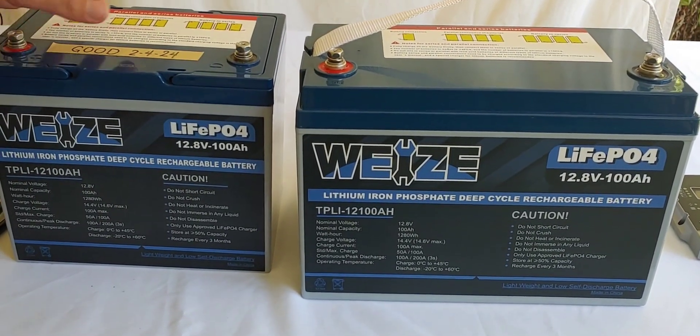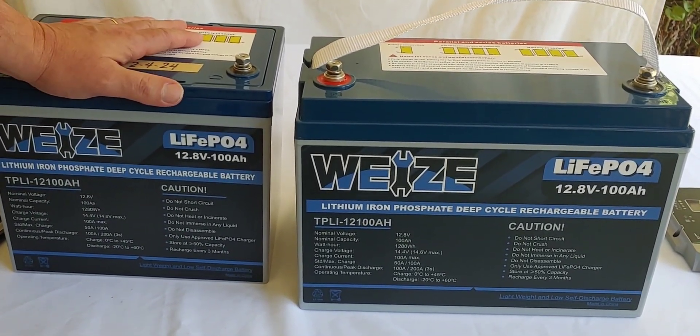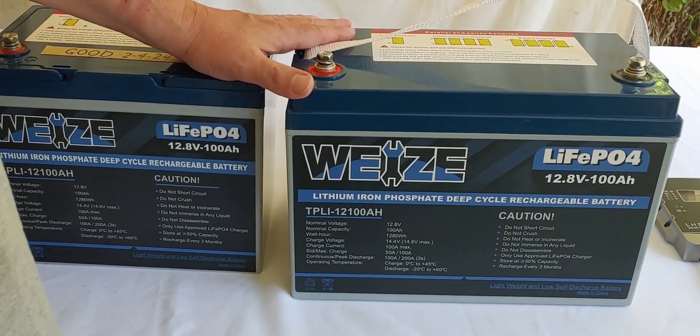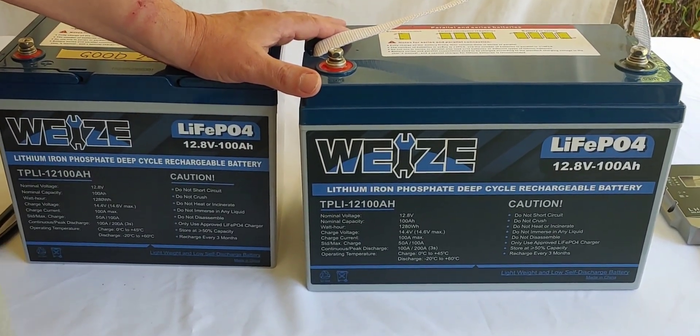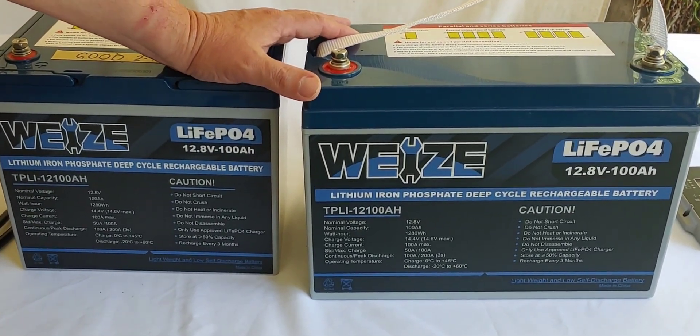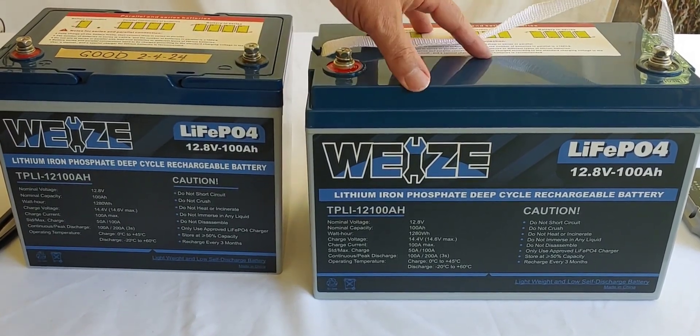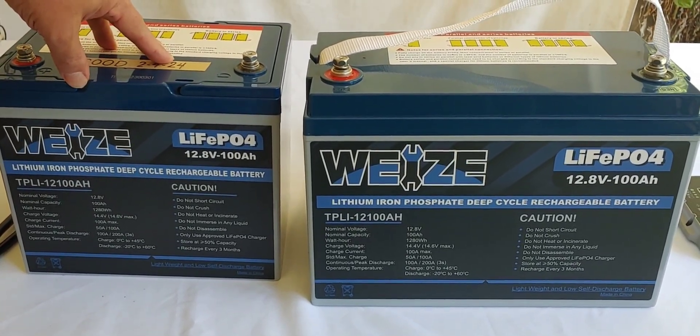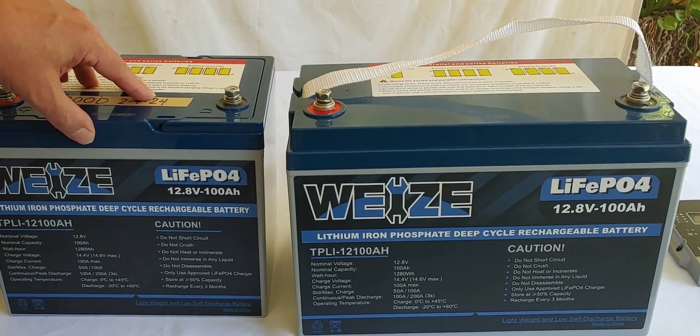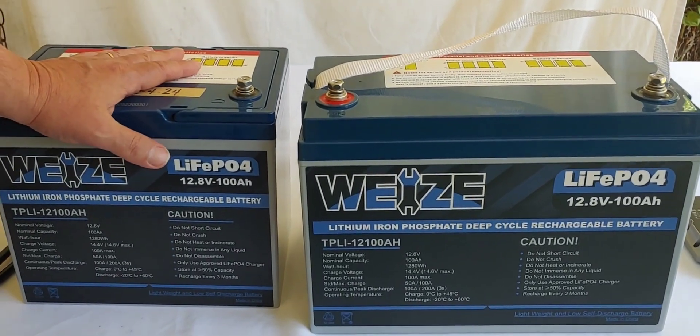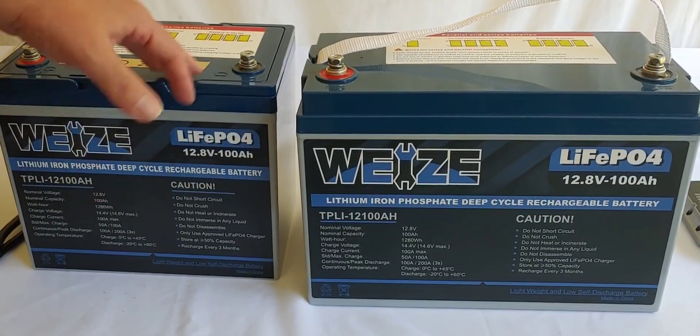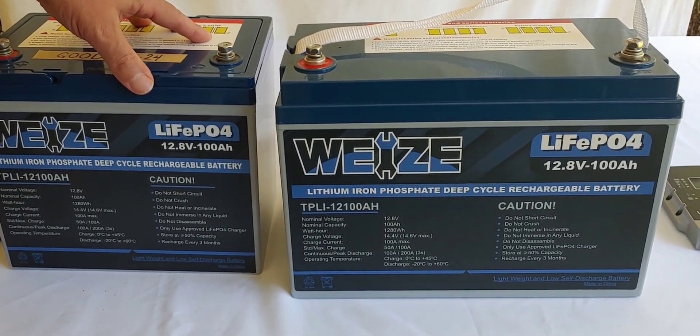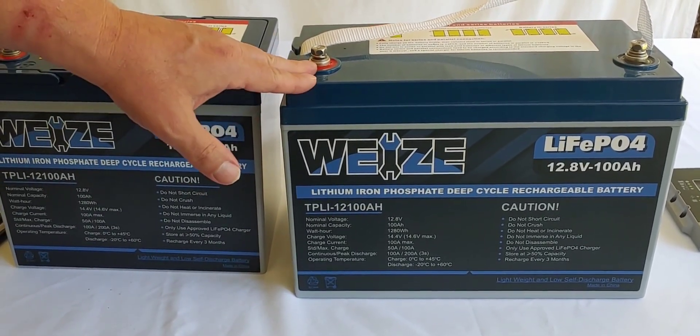Now, I recommend that you put batteries of the same type together, but not of the different chemistries. So putting two lithium batteries together is okay. I would not recommend you put a lithium battery and a lead acid battery, either a wet lead acid or an AGM, because the chemistry between the two is different. With these, though, the chemistry, even though the size is different, the chemistry is the same, and the battery management system is also going to function the same way. And for both of these, the battery management system is 100 amp hours. So it should be okay to put these two together, and it should operate just like two batteries of the exact same model type and size.